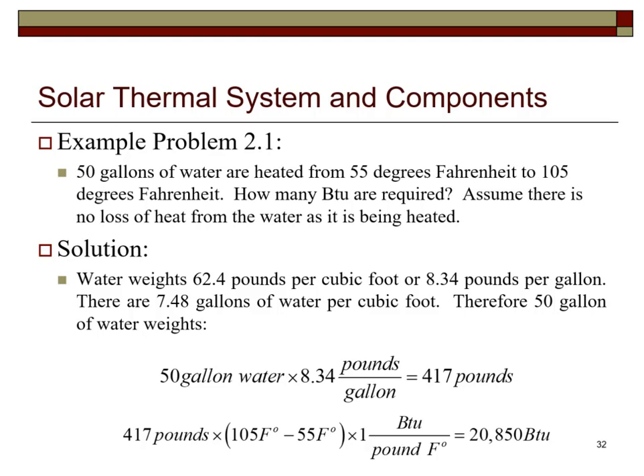Here we begin to demonstrate some valuable calculations with respect to solar thermal design. We look at how much energy it would take to heat 50 gallons of water from 55 degrees Fahrenheit to 105 degrees Fahrenheit. Water weighs 8.34 pounds per gallon. Therefore, 50 gallons of water weighs 417 pounds. Water has a specific heat of 1 BTU per pound degree Fahrenheit. 417 pounds multiplied by the temperature difference between 105 degrees Fahrenheit and 55 degrees Fahrenheit, and the specific heat of water, which is 1, yields 20,850 BTUs.